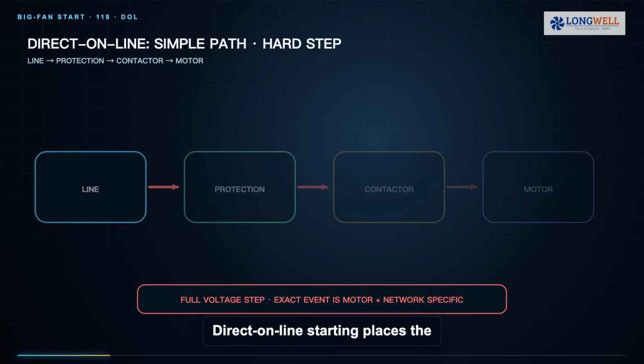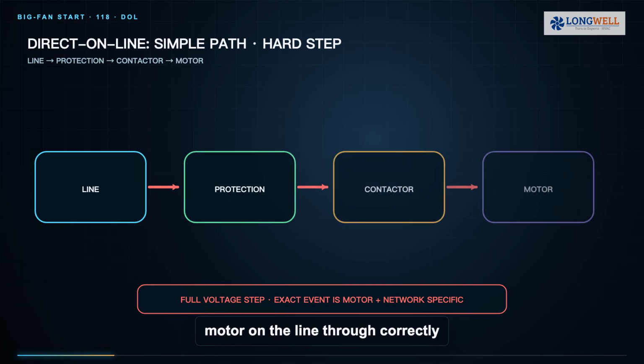Direct-on-line starting places the motor on the line through correctly engineered switching and protection. It is electrically simple and reaches full speed quickly, but the motor can draw several times rated current while accelerating, with a corresponding torque transient. The exact current, voltage dip and acceleration time come from the motor and network study, not from one universal multiple.